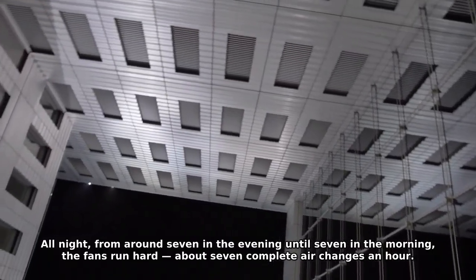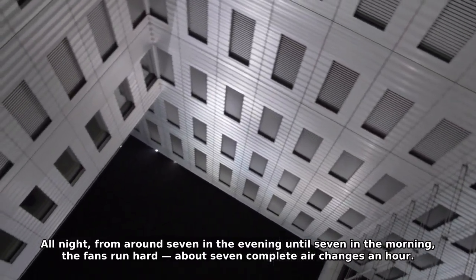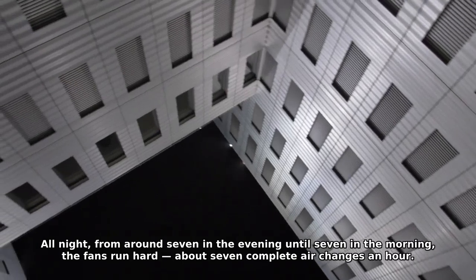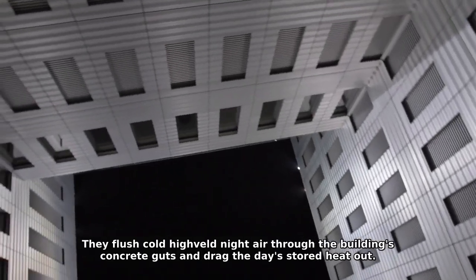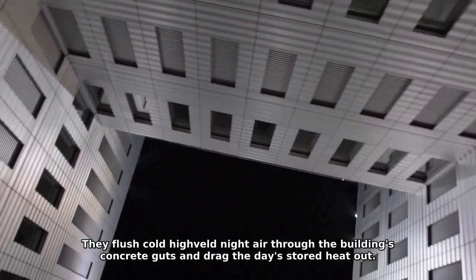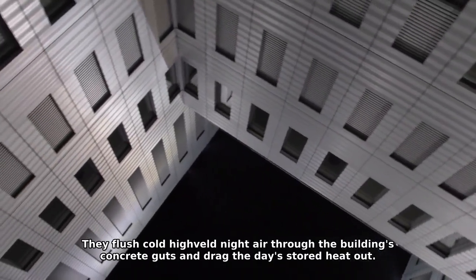All night, from around 7 in the evening until 7 in the morning, the fans run hard, about 7 complete air changes an hour. They flush cold, high-veld night air through the building's concrete guts and drag the day's stored heat out.